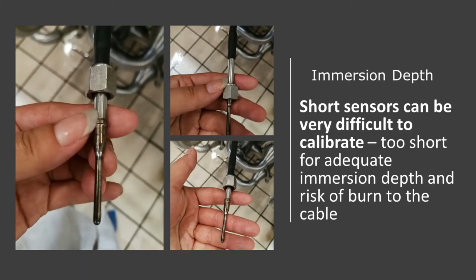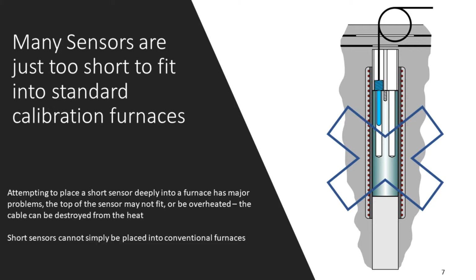However, short sensors can be very difficult to calibrate. They are often too short for adequate immersion depth, and there is a risk of damage to the cable. Many sensors are just too short to fit into standard calibration furnaces. Attempting to place them deeply enough into a furnace can cause major problems. The top of the sensor may not fit or could become overheated. The cables may also be damaged. Short sensors cannot simply be placed into conventional furnaces.